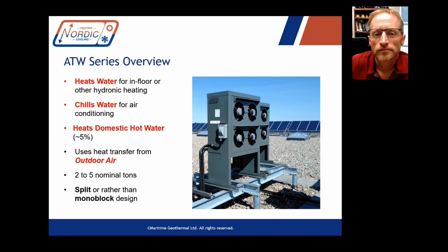Well, and then a couple of related questions. On that, if you wanted to scale to multifamily, I presume you could put these in series or parallel. I don't know what the setup is, but can you just scale them like that easily? So if you had any kind of hydronic heat pump, like a water-to-water heat pump or an air-to-water heat pump, it is very easy to put multiple units in parallel to satisfy larger loads than you would be able to satisfy with just a single unit. In the air-to-water case, it tops out at 5 tons in capacity. So larger houses will often require more than that.